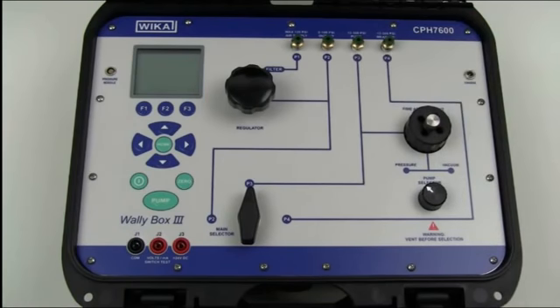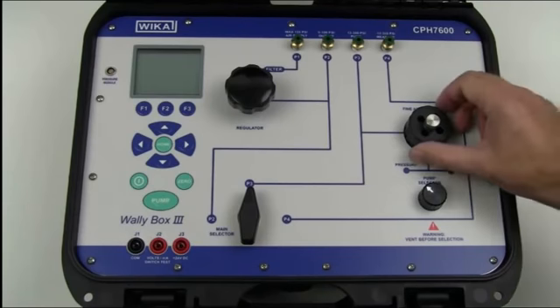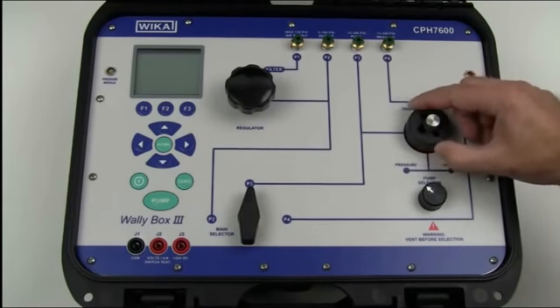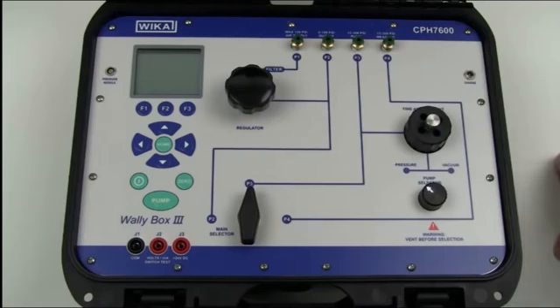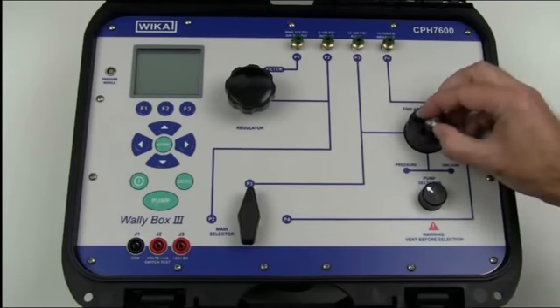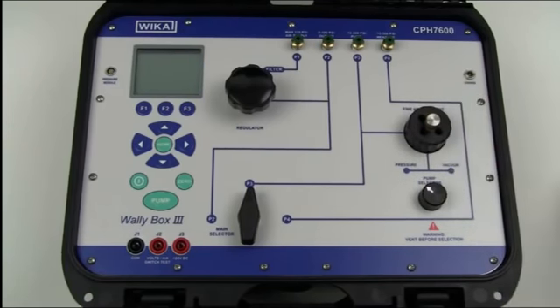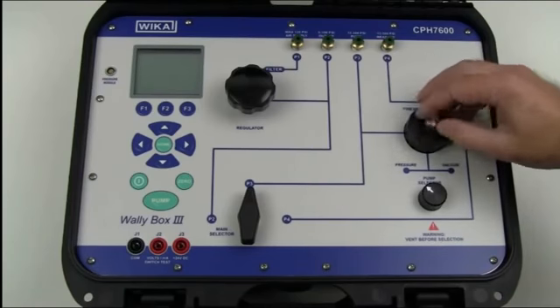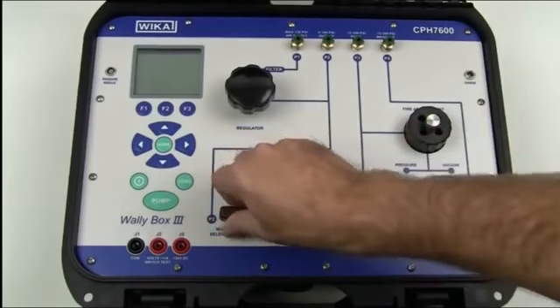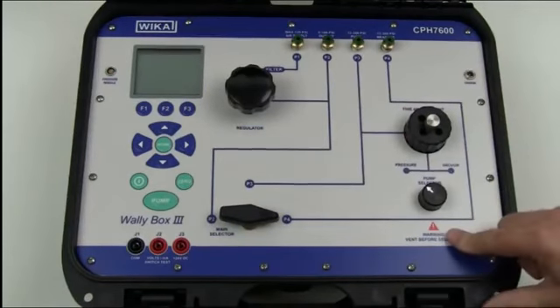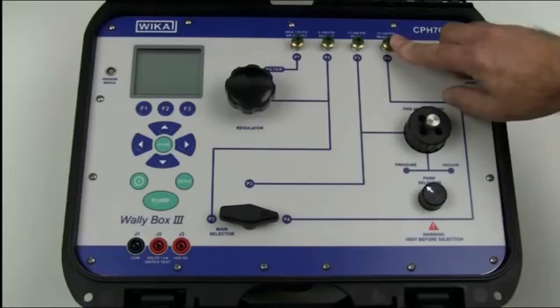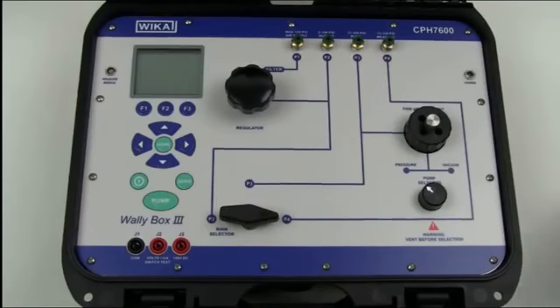The accuracy of the internal sensor is 0.025% of reading plus or minus 0.01% of full scale. With the fine adjustment you are able to adjust the volume and therefore adjust the pressure finely, and then with this valve you are able to vent the system. Then, by placing the main selector on position P4, you are able to use the internal sensor only and measure an input pneumatic signal of -12 to 300 psi.